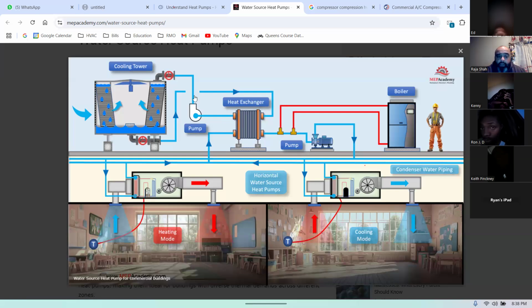What we're gonna do now is turn this fan off. Instead of shooting the water to the top, we're gonna shoot the water right into this basin. Instead of coming up here, there's going to be a bypass - it's going to go right to the bottom. So it comes out here, it's going to cool down a little bit, and then it's going to go back through this heat exchanger.